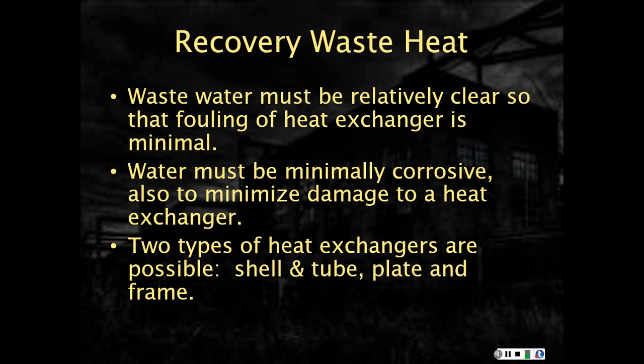Now, there are two types of heat exchangers, as you recall from your heat exchanger section in your 462 or 362 class: shell and tube, and plate and frame. Shell and tube is a little more tolerant of more junky water. Unfortunately, it's one size when you start. Plate and frame has a lot more variability to it.